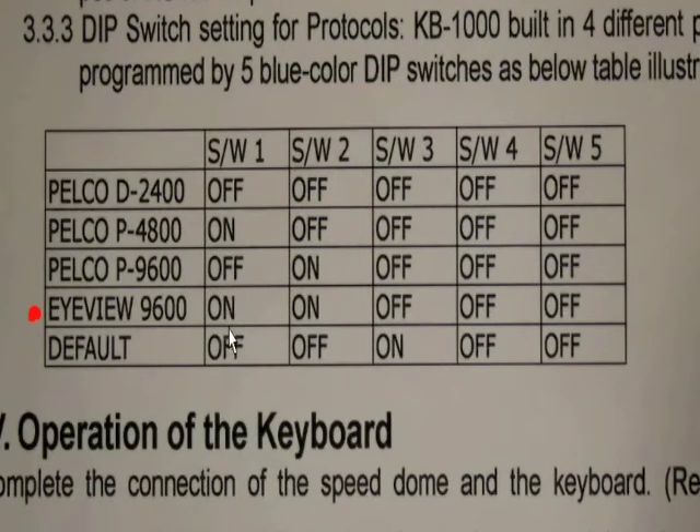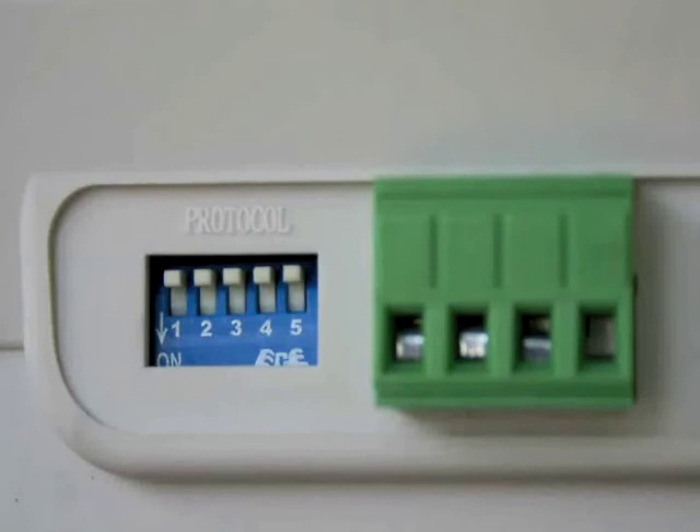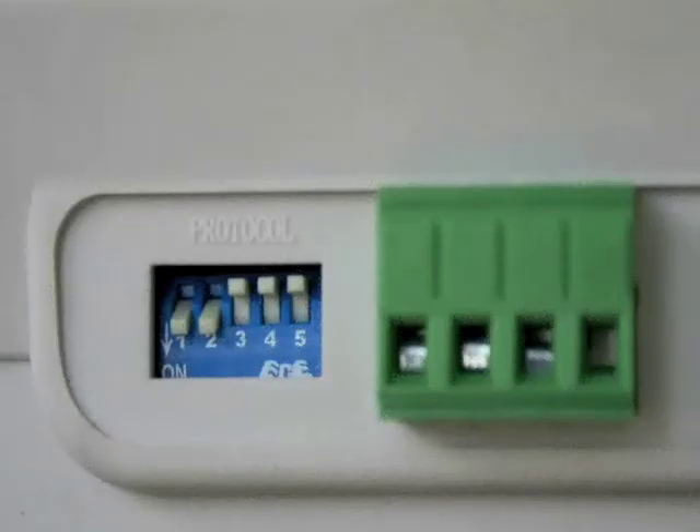On the controller, the chart says that for EyeView you have switch 1 down, switch 2 down, and switches 3, 4 and 5 up or in the off position. Once again, you locate the switches — here they are in the off position — and simply flick switch 1 and 2 down. It's now all set for EyeView communication language.